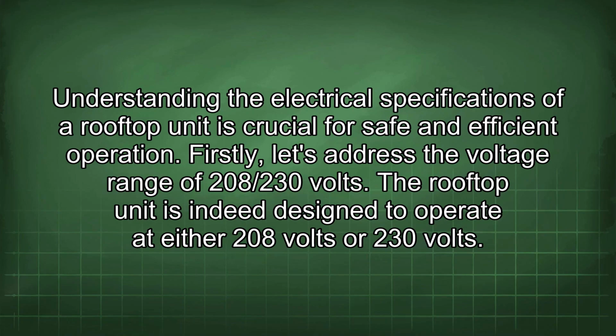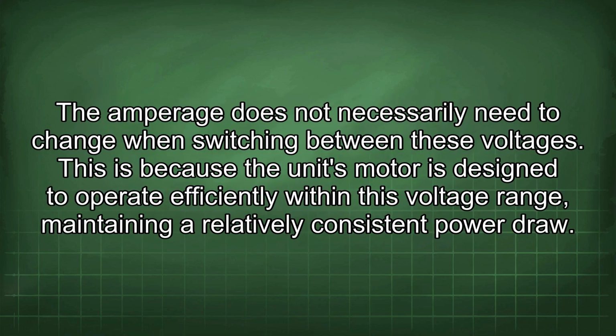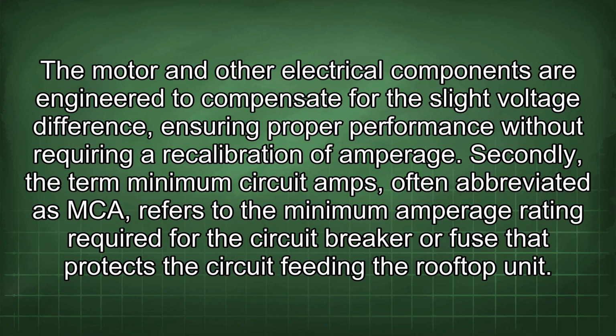Understanding the electrical specifications of a rooftop unit is crucial for safe and efficient operation. Firstly, let's address the voltage range of 208/230 volts. The rooftop unit is indeed designed to operate at either 208 volts or 230 volts. The amperage does not necessarily need to change when switching between these voltages. This is because the unit's motor is designed to operate efficiently within this voltage range, maintaining a relatively consistent power draw. The motor and other electrical components are engineered to compensate for the slight voltage difference, ensuring proper performance without requiring a recalibration of amperage.